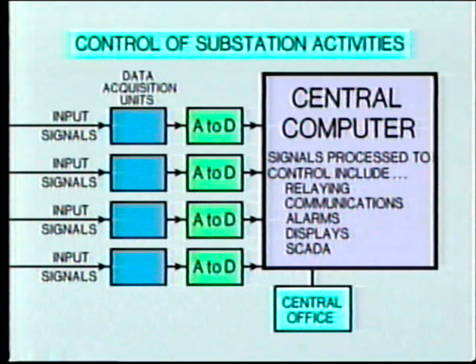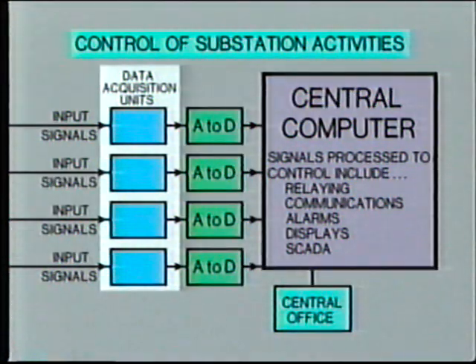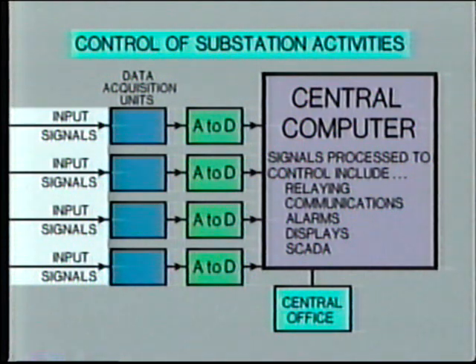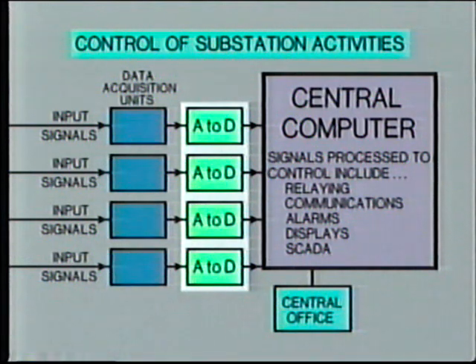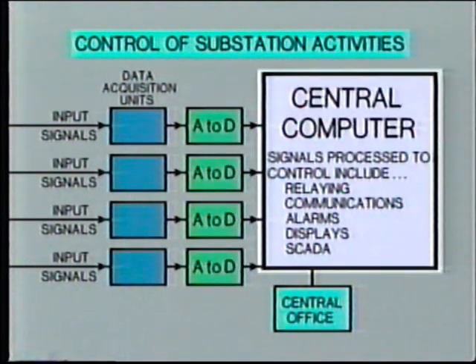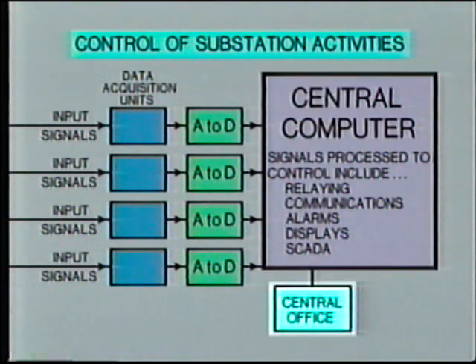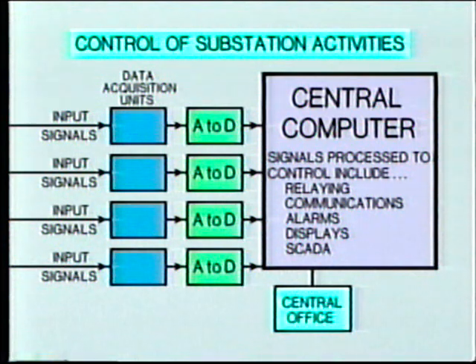This block diagram shows the principle of the scheme. Data acquisition units are installed at various locations throughout the substation. Each of these receives voltage and current signals from the nearby circuits, such as distribution lines, bus arrangements, transformers, and so on. The voltage and current signals are then converted to digital signals, and these in turn are transferred by multiplexing to the central computer located inside the control house. The central computer can then process all of these signals according to the various functions. At the same time, it will be connected by a modem to the remote central office. You'll recognize this as similar to the SCADA system that we have discussed in other video training programs.